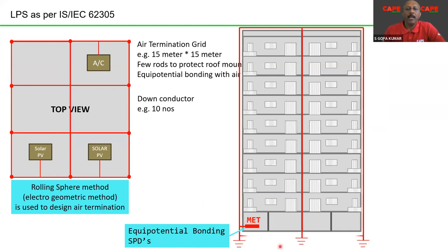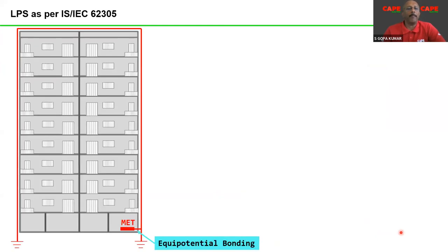Now, this kind of vertical electrodes, one of the techniques which has been an improved version of the earthing system, is called a type B earthing. Probably you can see here all the earth electrodes are interconnected together. One of the techniques included is the ring earth. That means you make an earth electrode all around the building as a ring. That is more efficient than putting individual vertical or horizontal earth electrodes. So type B ring or foundation earthing is more advantageous for a critical building or a high-rise building. So basically, your lightning protection consists of air termination, down conductor, earthing, and SPD.